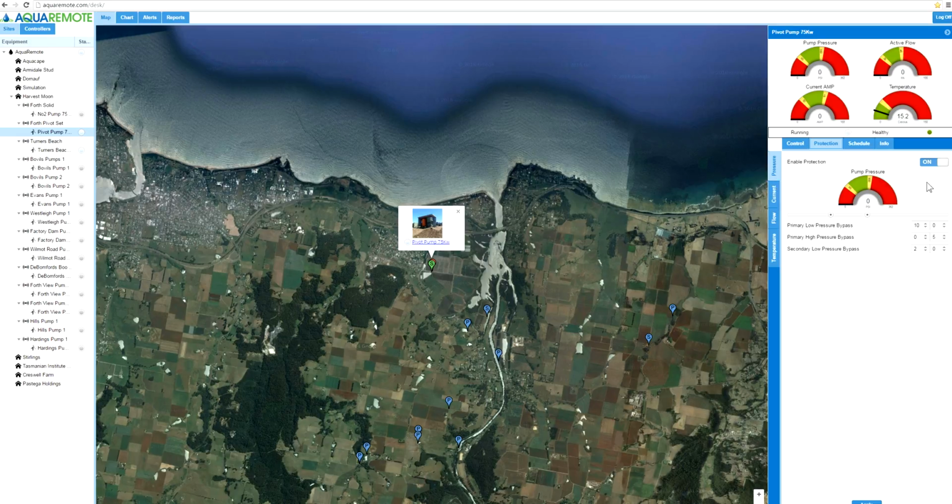Looking at the pressure protection screen, there's an enable disable function. So that means that if it's enabled or on via the toggle, this protection parameter will be active. So then therefore the thresholds that are applied and the timers that are applied will be active, and the system will work accordingly to those. So you have a low pressure set point and a high pressure set point. Ability to manipulate and change this to what you want.